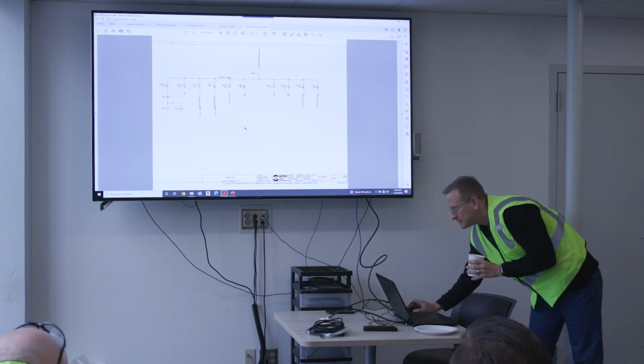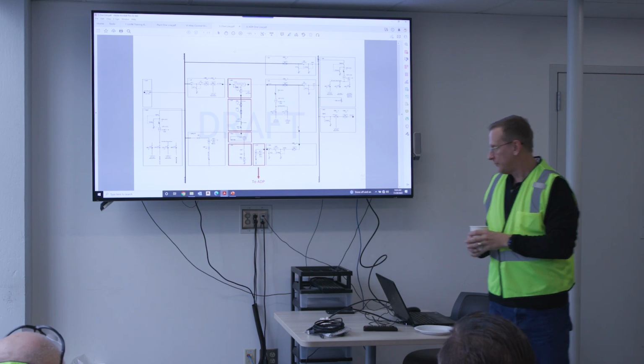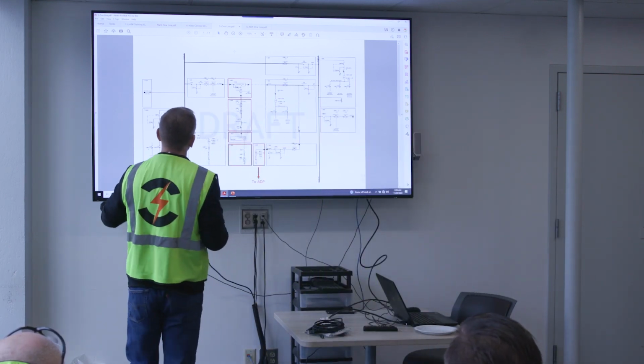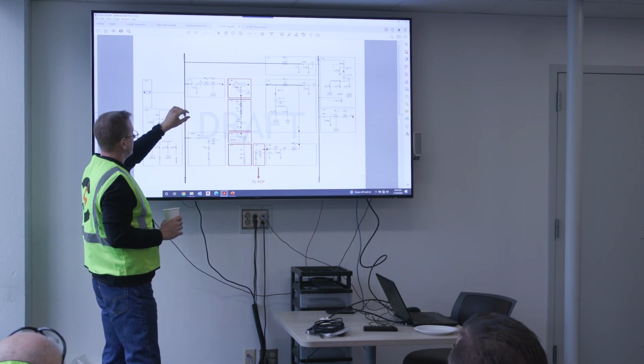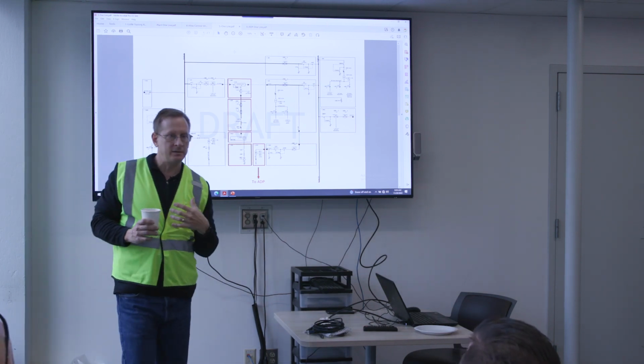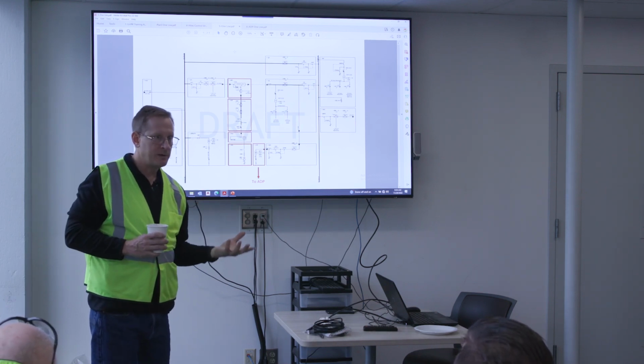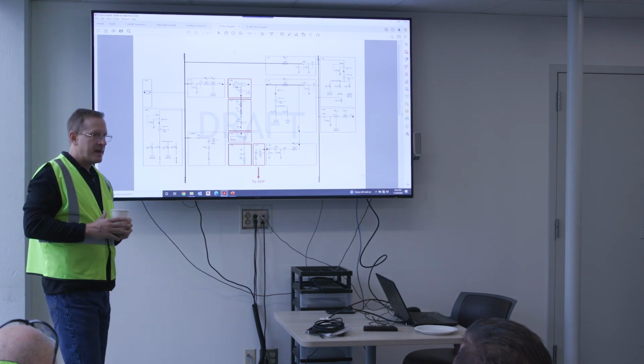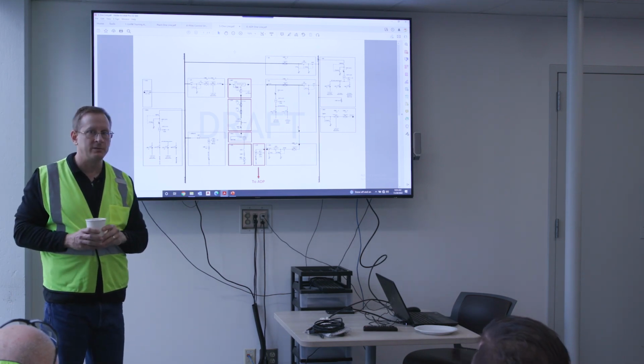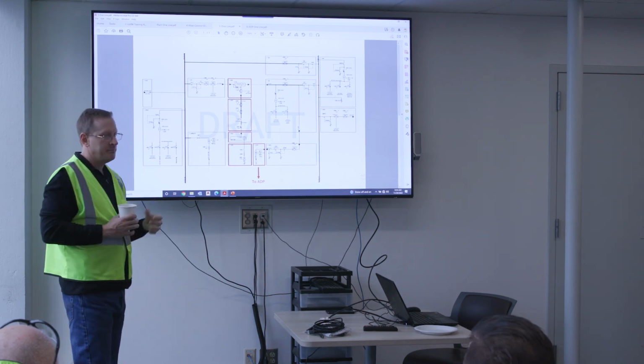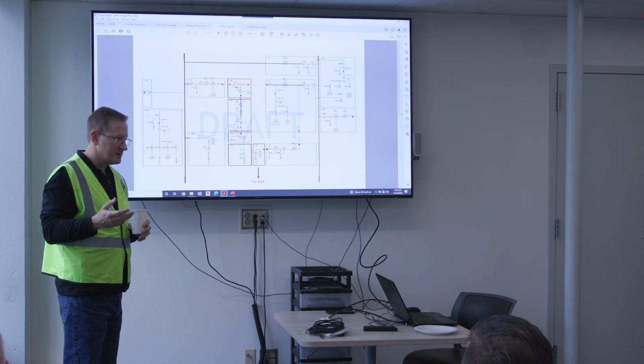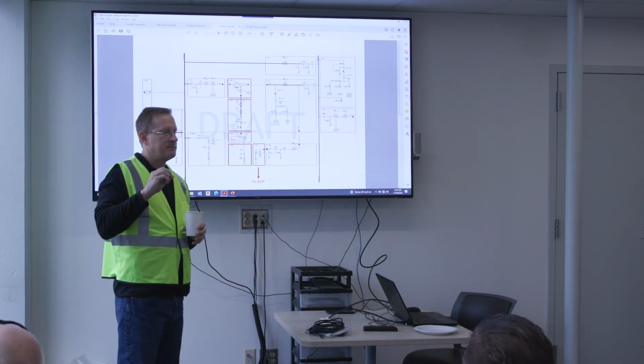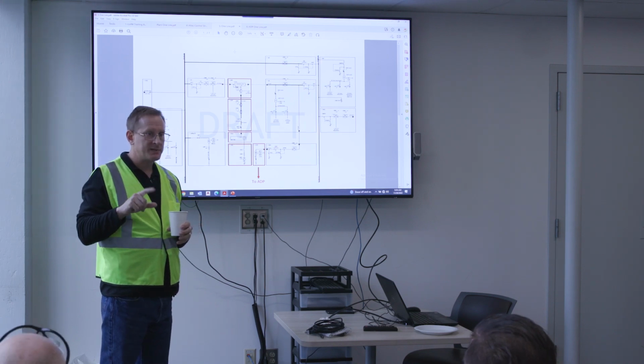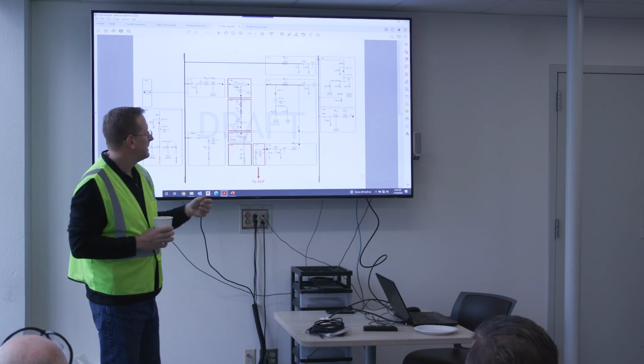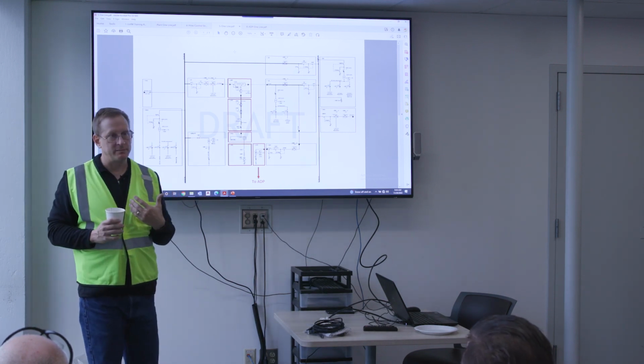The switchgear itself and the controls for the breakers, the switchgear controls that actually send voltage to the breakers to open and close them, for the trip coils and for the closing coils. That's 125 volt DC power that is utilized to operate those breakers. Our PLC will basically initiate 24 volt control voltage to certain relays, which then will close or open, which will port 125 volt DC for the coils to operate the breakers, to open and close them.